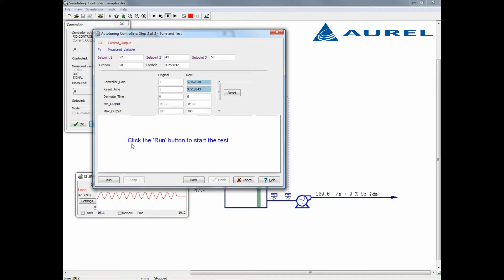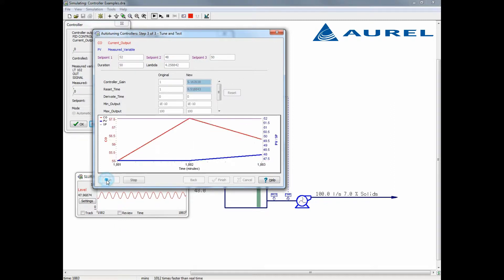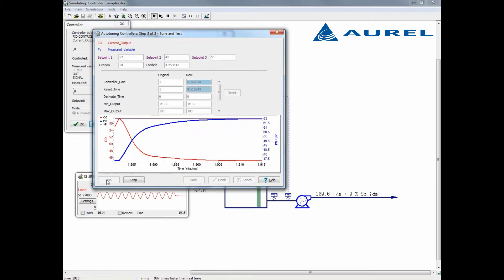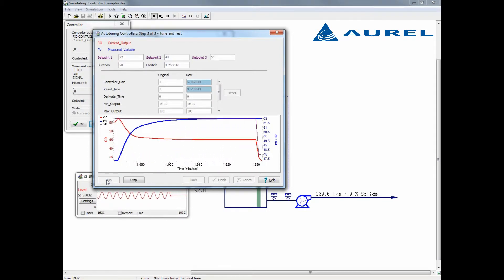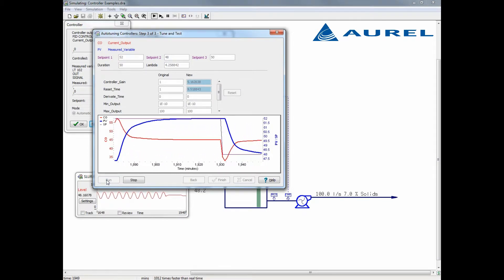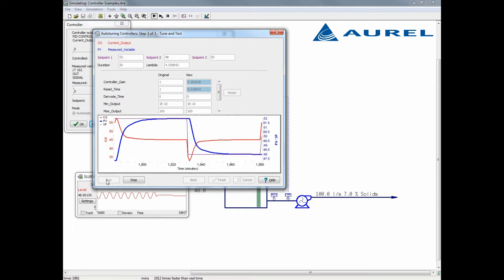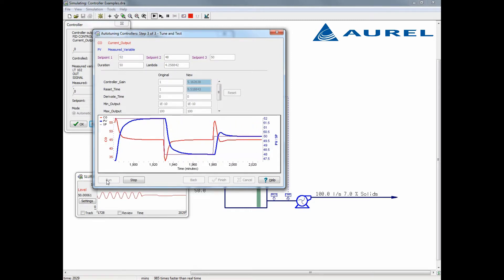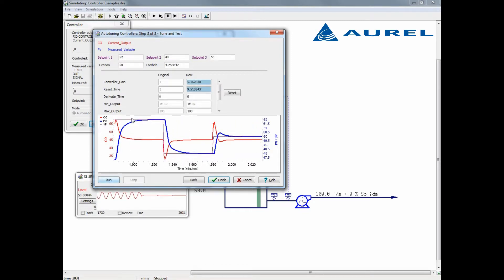We can select run to see the controller performing. Here we see the controller seeking to achieve new set points. The one parameter I want to note here is the lambda value. This is a defined parameter for the lambda tuning method and typically is the closed loop time constant. If you want the controller to act faster or slower than what is suggested by the autotune, you can adjust this lambda parameter here, provided your bump tests identify the process dynamic correctly.